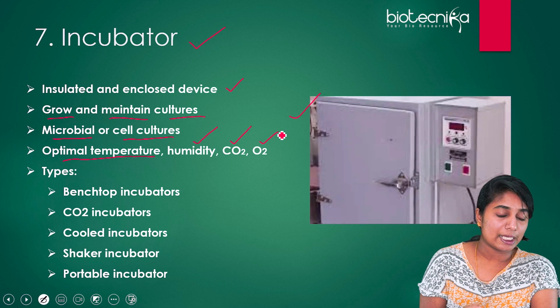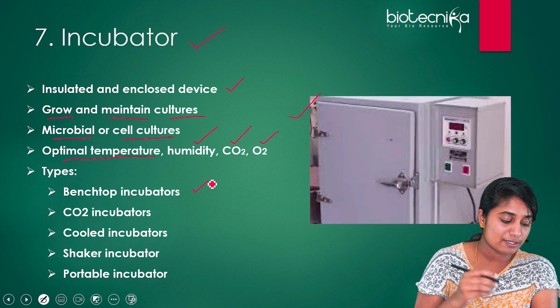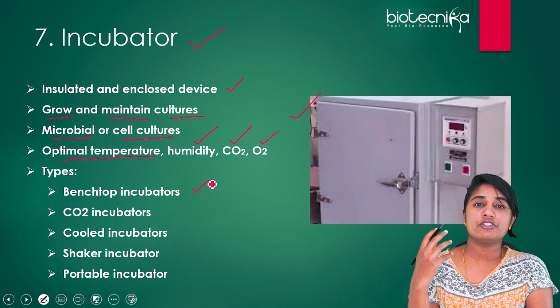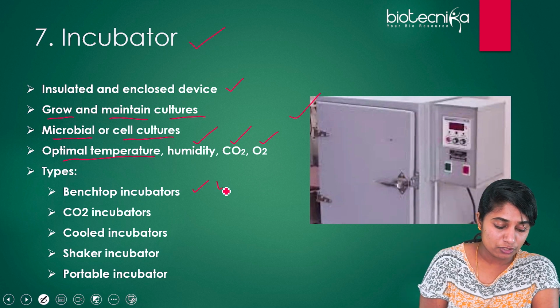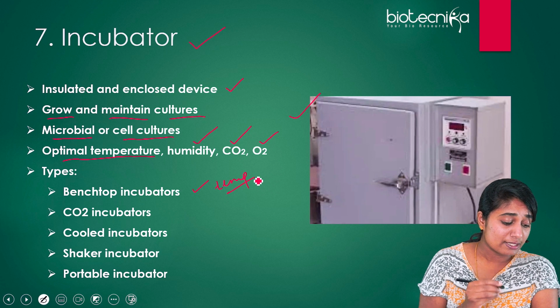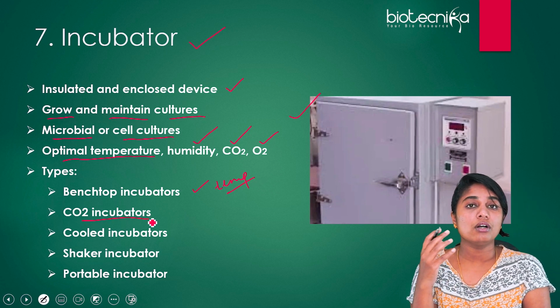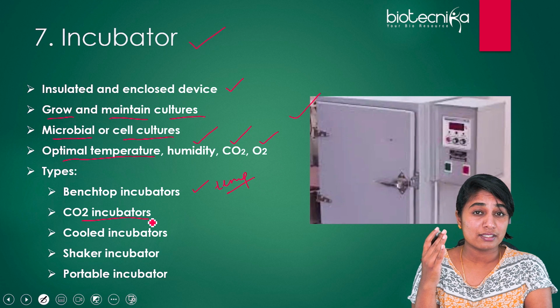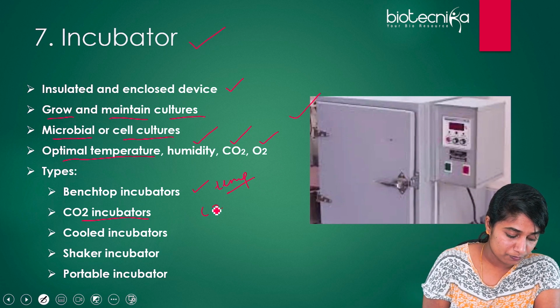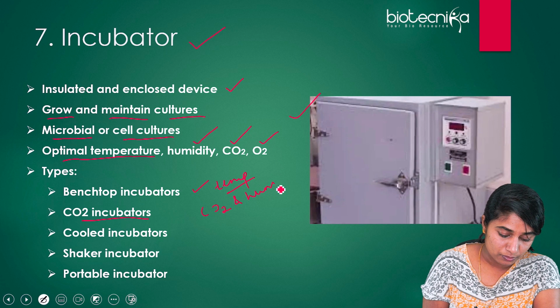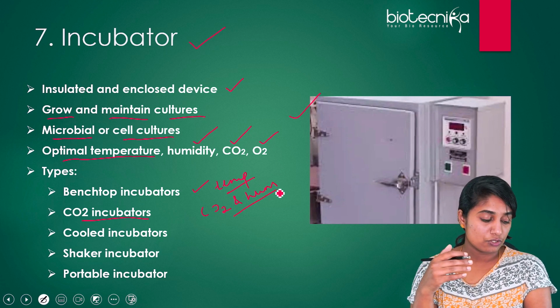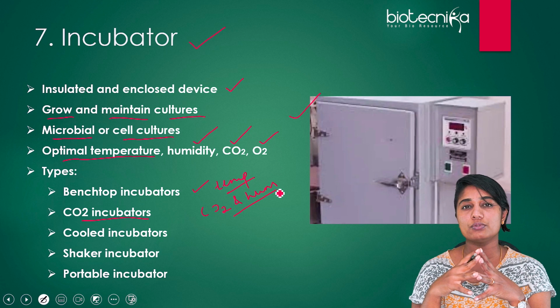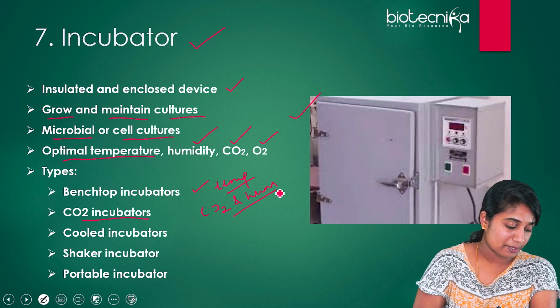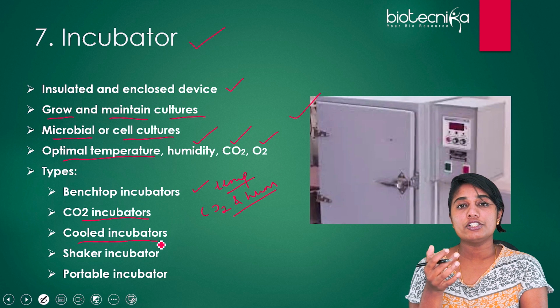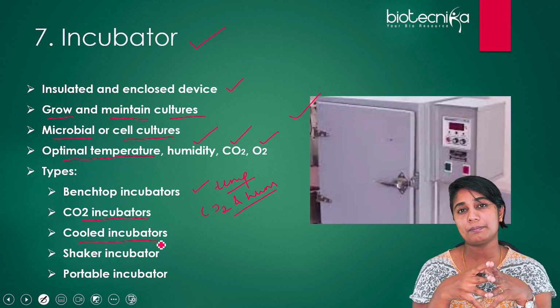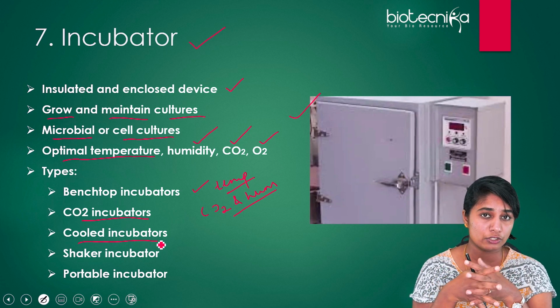Now, the different types of incubator that are found: first is the benchtop incubator, which generally controls the temperature alone, right. The second is the CO2 incubator, where along with temperature, even the CO2 as well as the humidity is being controlled, right? So these two are the additional features of a CO2 incubator, which is majorly used for cell culture experimentations. Next is the cooled incubator, where your culture requires a below optimum temperature. So here we use a refrigerated incubator, right?